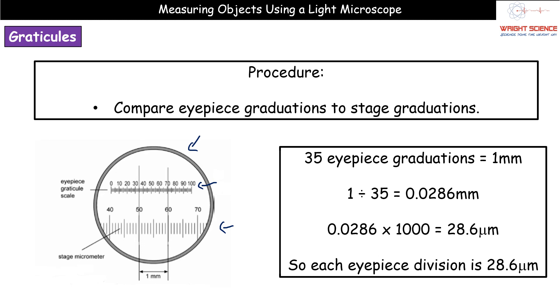Now once you've calibrated that you could then place your specimen under that same objective lens and then work out how many of those eyepiece little graduations go from one side of an object to another. We can then just multiply it by 28.6 and we now know the size of that particular object under the microscope.